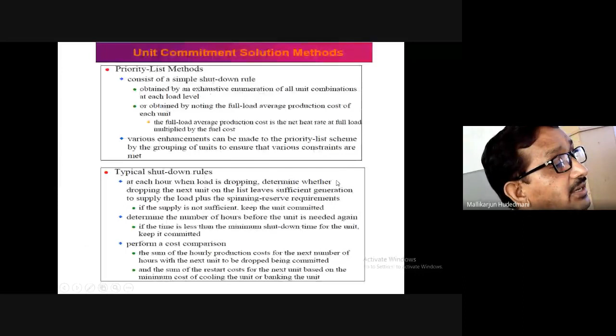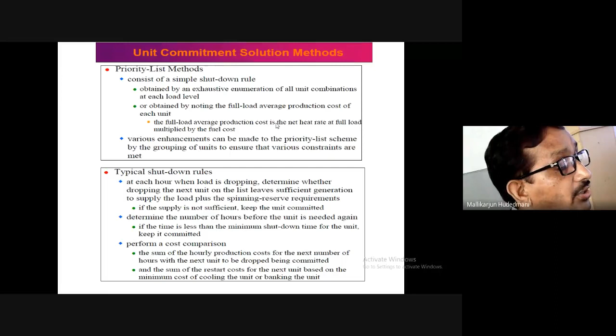This is called following the shutdown rule. Priority wise, the one which is costlier should be taken out, then the one which is lesser than that, and the least one should be maintained. This is the gist of the priority list method for a certain minimum to maximum capacity. The same thing has been presented over here. The priority listing method follows a simple shutdown rule, and it has to work out the average production cost of the machine from minimum to maximum and pair them accordingly.